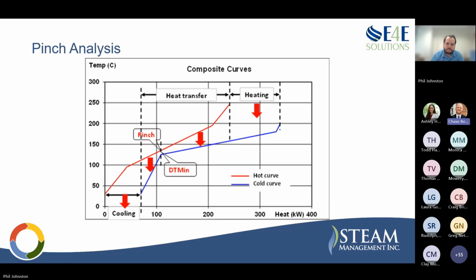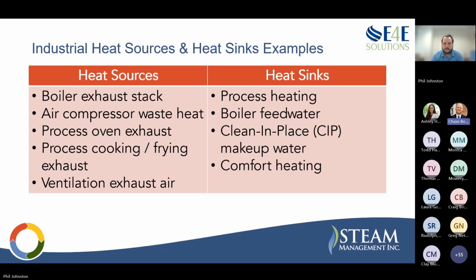So my impression, Phil, and this also agrees with your list there, is that in most applications you're really needing a high temperature heat source. So with air source and ground source heat sinks, there's too much lift, at least when you're talking about generating steam or high temperature water. Is that fair to say? Yeah, the temperatures can vary. The golden goose is a low temperature heat sink, because then you can throw pretty much anything at it from a heat recovery standpoint. But those are fewer and far between in an industrial setting.